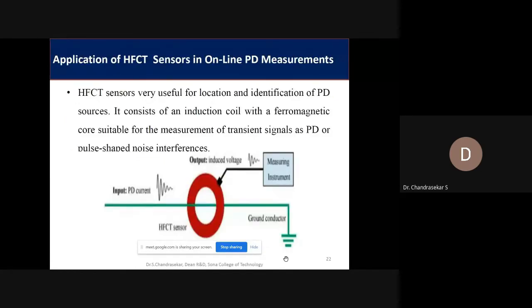So this is a simple measuring concept of the HFCT sensors, the high frequency current transformer sensors, in the case of online PD measurement. Okay, so through the ground line, we need to connect this HFCT sensor, and through the BNC cable, we can connect it with any measuring instrument. Even a simple CRO you can measure, or if you want to go for any advanced PD systems, then we need to place a permanent data capturing system, and then that should be interfaced with the cloud, and then you can process it remotely. So in such a way, we can connect this HFCT sensor easily.